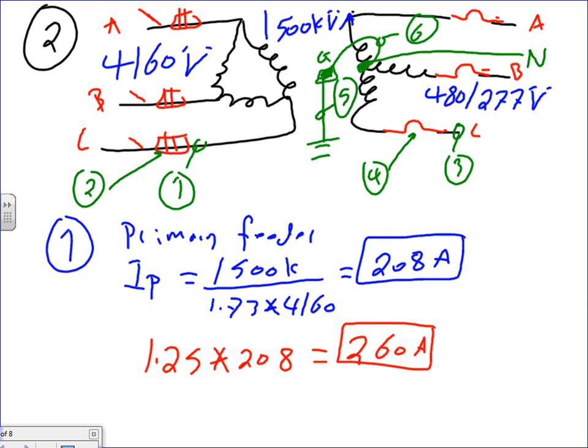What do you do with the 260 amp? You take it to which table? Let me see who's going to be making the mistake now. Wrong. Does 310.16 go up higher than 600 volt? Oh, no. That's a catch-22. 310.16 does not cover 4160. Look at the voltage. That's a high voltage cable.